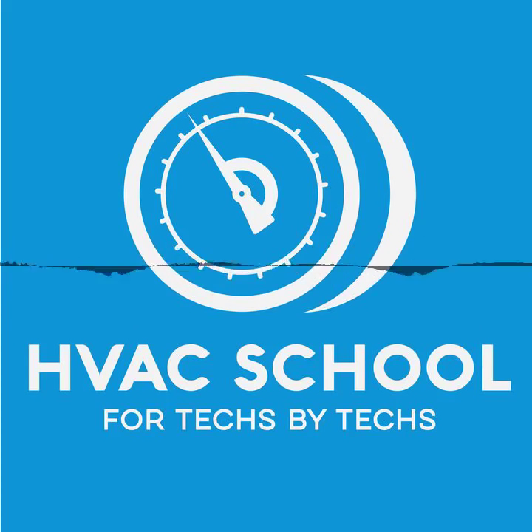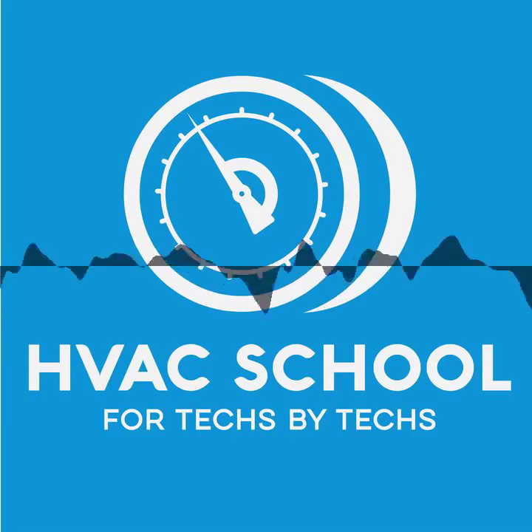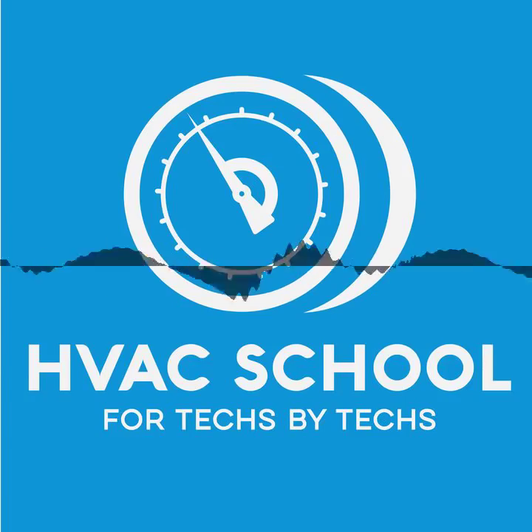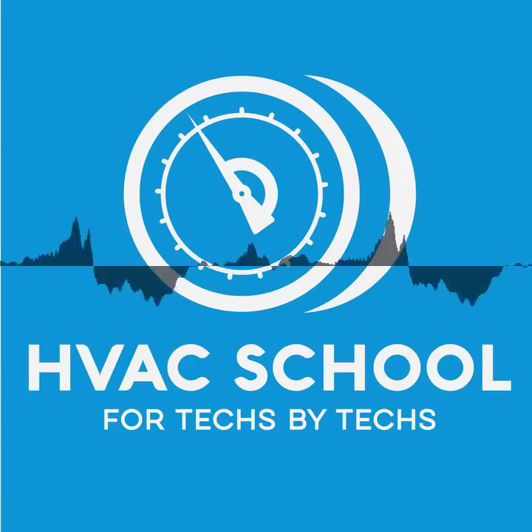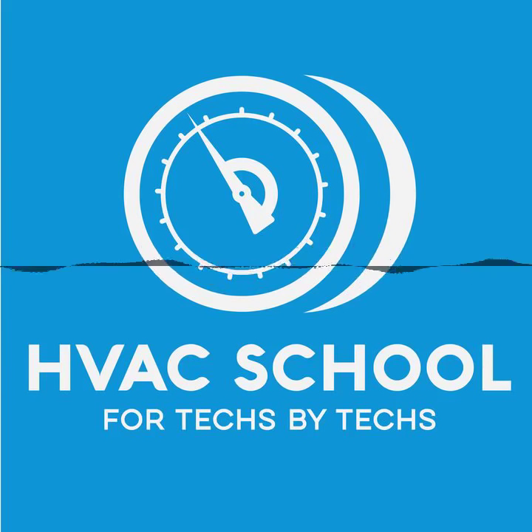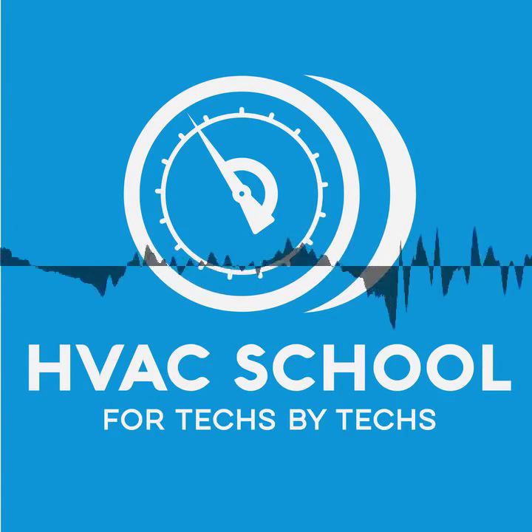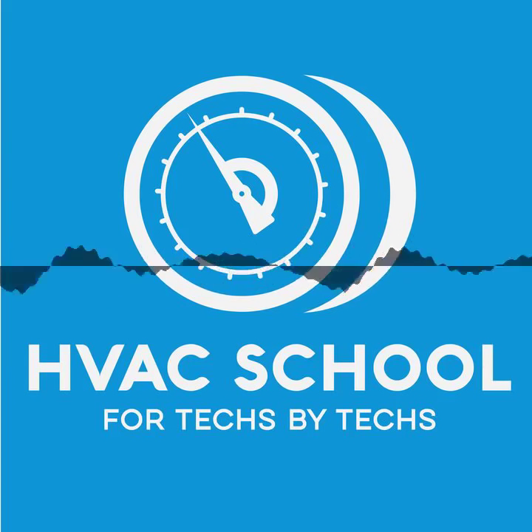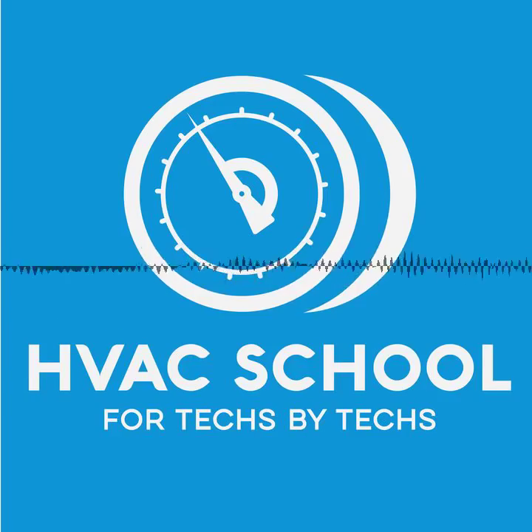Okay. So a compressor takes this vapor, which is very, I want to use the opposite of dense, very loose. These molecules are separated and it's low temperature. Then you throw it into the head of this compressor and you slam these molecules together. Yeah. And obviously as the pressure rises, it goes against the discharge line pressure, right? And once the pressure is above the discharge line pressure, a valve opens up and allows the vapor refrigerant to flow through into the discharge line, right? Right. That is the traditional reciprocating compressor, when you have valves in it. So the pressure in the head obviously has to go higher than what's in the discharge line, like Keiran just said, in a reciprocating compressor. And then it opens that valve and that refrigerant goes out.